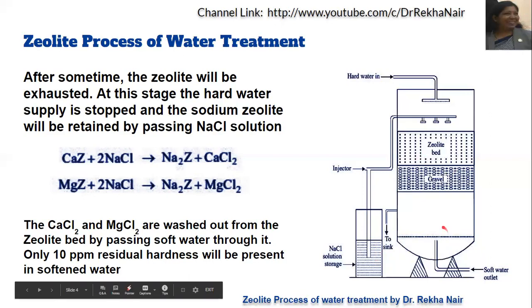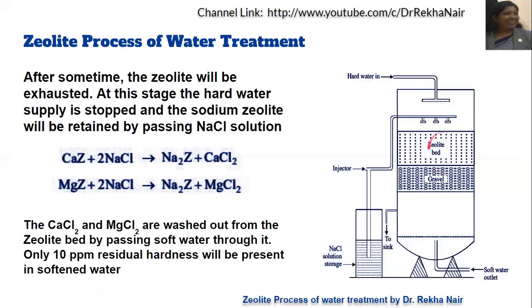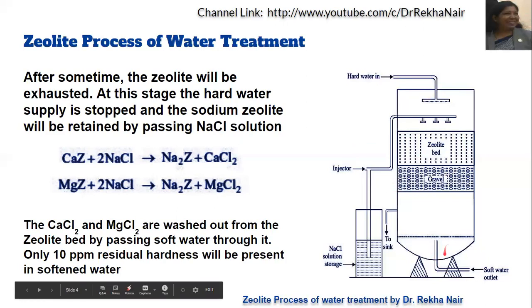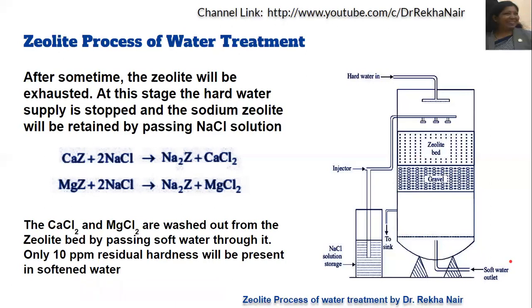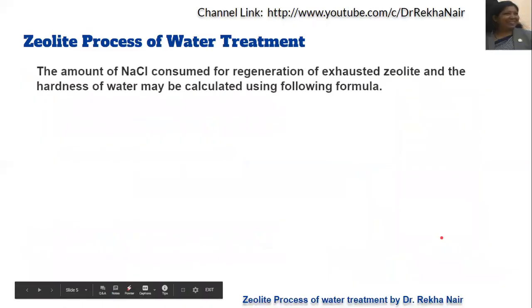After this process, only 10 ppm of residual hardness will be present. Once the sodium zeolite is regenerated, the hard water supply is resumed and we get softened water again, which contains only 10 ppm of residual hardness. This is better compared to the lime-soda process.